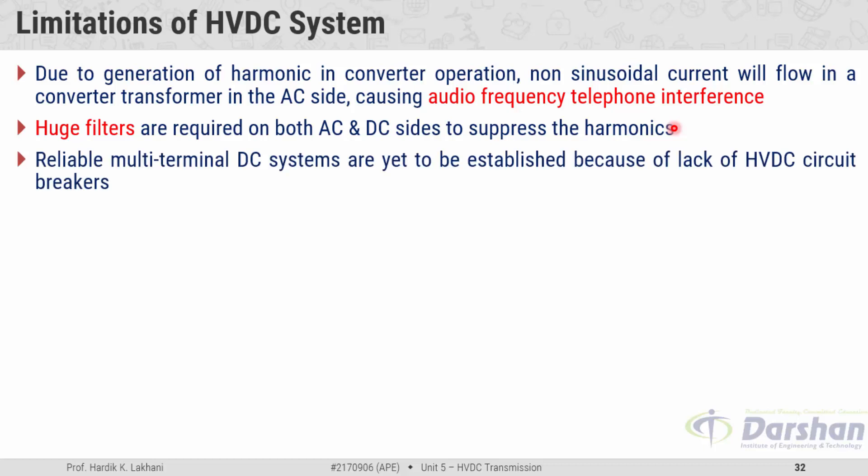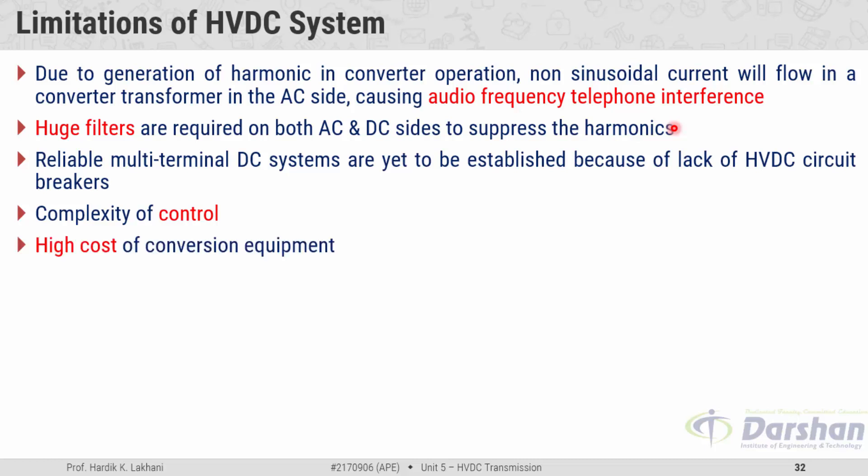Reliable multi-terminal DC systems are yet to be established because there are no HVDC circuit breakers available. The complexity of control is another limitation — to control the magnitude and direction of power, many equipment items must be controlled in synchronism, which is the biggest challenge. The highest cost of conversion equipment is also a limitation; the most costly part in an HVDC system is the valves, which are thyristors or IGBTs used to construct the rectifier or inverter.